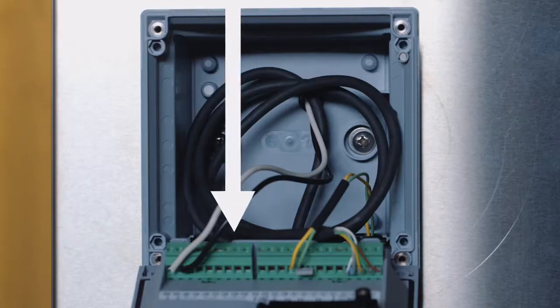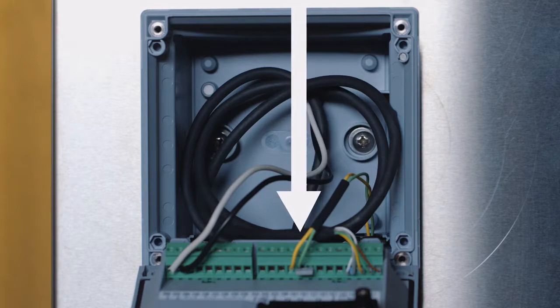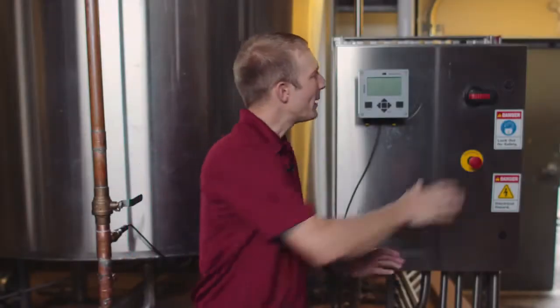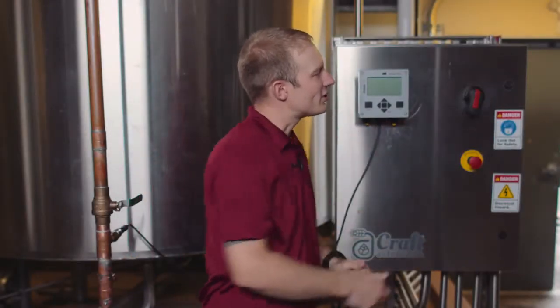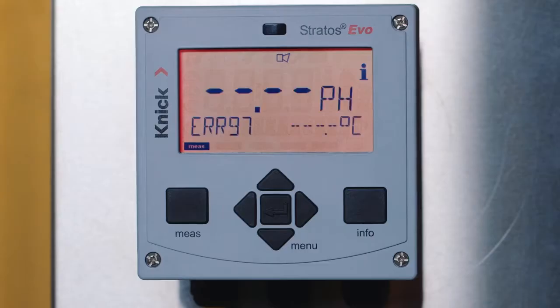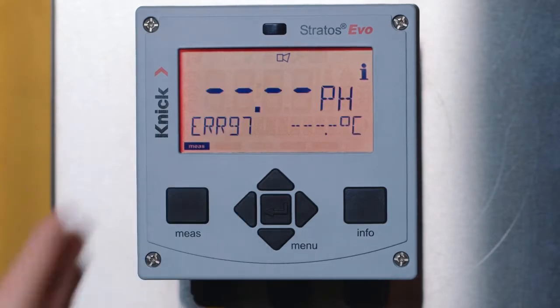Before you begin, ensure that your power supply, MemoSense sensor, and any outputs that you are utilizing are connected to the main terminal block on the transmitter. Let's get started by configuring your sensor within your Stratos Evo transmitter. You'll notice that we currently have an error and the screen is red. This is because we have not yet configured the transmitter for a MemoSense sensor.